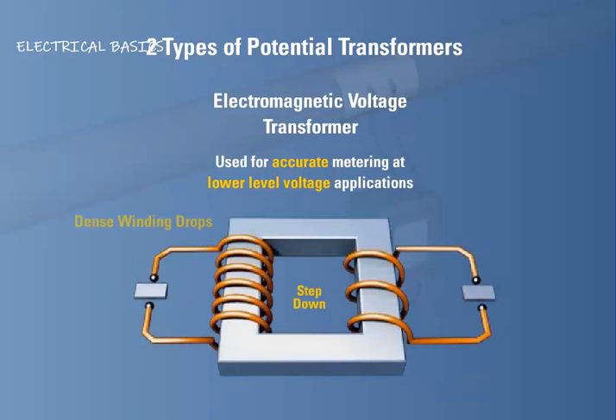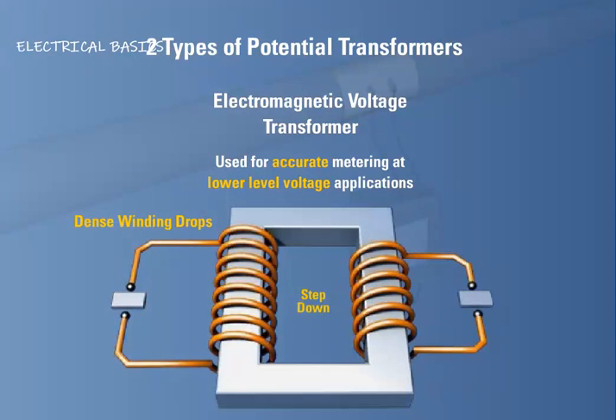Electromagnetic voltage transformers have dense winding designs to accurately scale down the voltage and ensure the ratio is consistent for all variations in the input voltage. Due to the small amount of voltage drops per winding, electromagnetic voltage transformers increase in size as the rated primary voltage increases. Likewise, the cost of electromagnetic voltage transformers tends to increase at a disproportionate rate to the primary voltage rating.